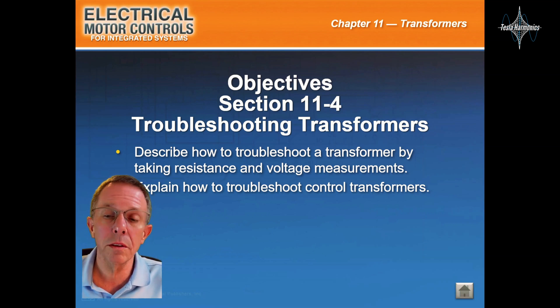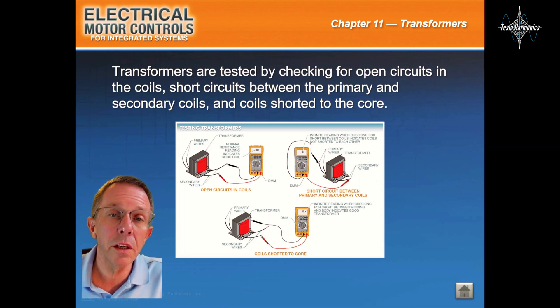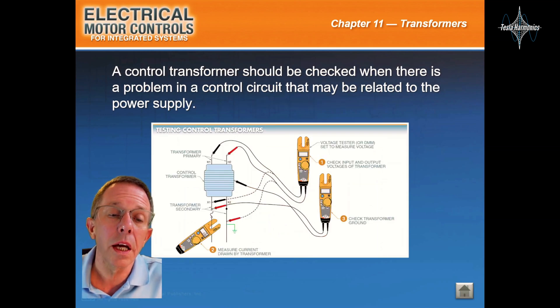Transformer troubleshooting. Transformers are tested by checking for open circuits in the coils, short circuits between the primary and secondary coils, and coils shorted to the core. A control transformer should be checked when there is a problem in a control circuit that may be related to the power supply.